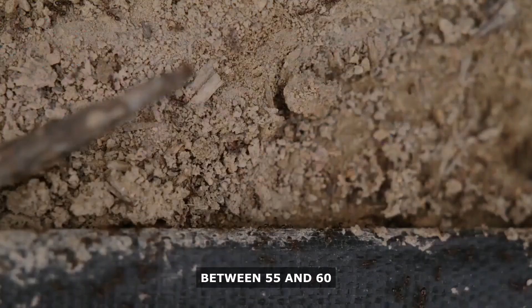Now, you are probably wondering, how much does the water temperature actually drop? That depends on several variables: the length of your coil, the flow rate of your water, the soil composition, the ambient air temperature, and the season. But here is what the research consistently shows. In midsummer, when the air temperature outside is 95 degrees, water that enters your buried loop at 70 degrees will exit at somewhere between 55 and 60 degrees. That is a drop of 10 to 15 degrees. When that cool water travels through your indoor radiator and a fan moves room air across it, that air can drop another 10 to 15 degrees. So you are looking at reducing your indoor temperature by 20 to 30 degrees without touching your central air conditioner.